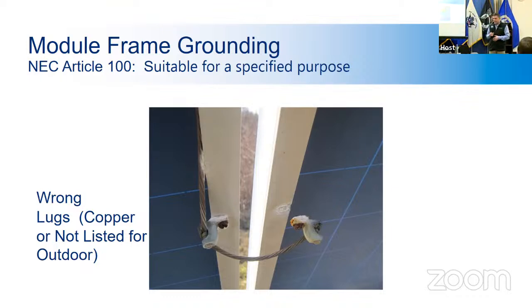You want to make sure that all the equipment for these systems is rated for outdoor use, because if not, it'll fail. And you can see up here, hopefully you can see these, there's corrosion right here between the aluminum frame and the grounding wire. So eventually, probably this whole section would be disconnected, and this panel might not even be connected into the grounding system.